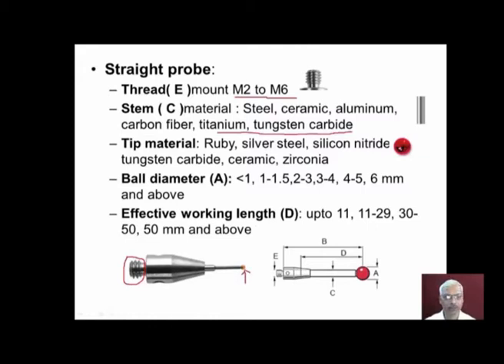This is the probe tip. Probe tips are available with different tip material like ruby, silver steel, silicon nitride, tungsten carbide, ceramic and zirconia. And tips are available with different shapes also. So this shows a ball type tip, and balls of different diameters up to 6 mm and above are available depending upon the inspection requirements. So effective working length of the probe is D. So the probes of different working lengths are available up to 11 millimeter, 11 to 29 millimeter, 30 to 50 and 50 mm and above. So depending upon the application, we can select probes of different length.